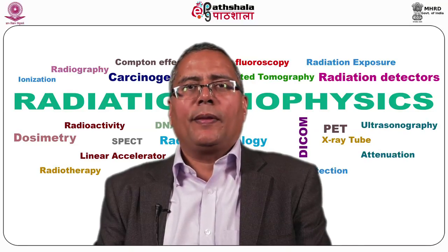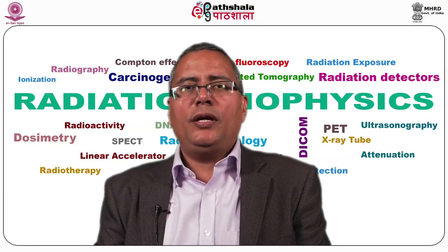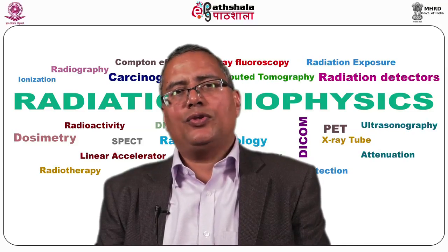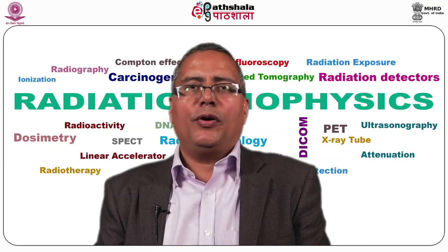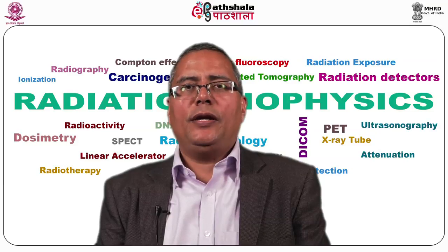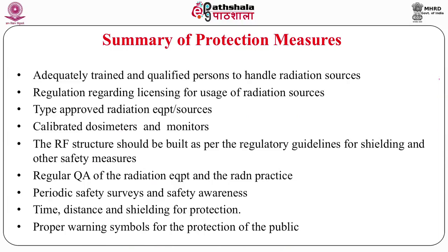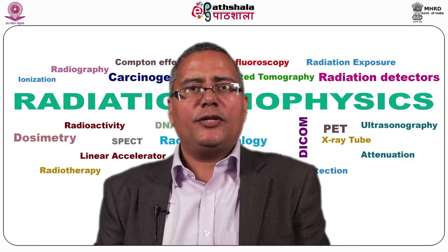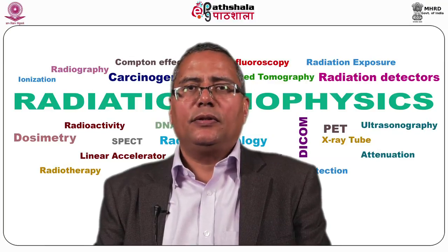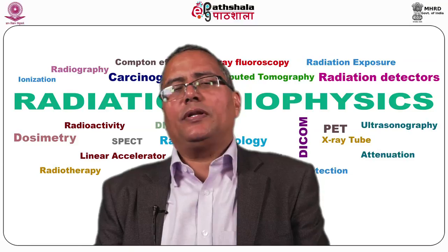Number 2, the radiation facility should also be as per the guidelines or safety codes of AERB, that is, the shielding, the monitoring equipment, and all safety measures should be in place. Regular quality assurance of the radiation generating equipment and of the entire practice should be carried out at periodic intervals. All equipment should be calibrated, radiation measuring equipment should be calibrated. Radiation warning symbols should be placed at ubiquitous places for the public and also for all the radiation workers. The radiation workers should follow the practice of ensuring safety as per the guidelines.